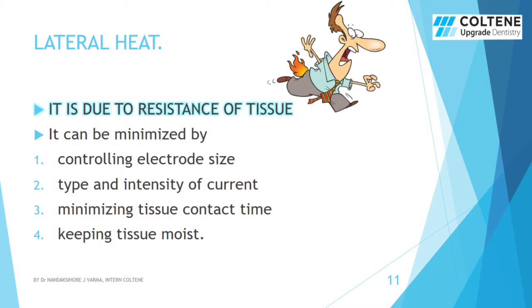Lateral heat is the heat which is caused in the surrounding area of the usage spot of electrodes, caused due to the resistance offered by the tissues. How can we minimize it? By controlling the electrode size and making it smaller, the lateral heat can be reduced. Type and intensity of current, minimizing tissue contact time — just in seconds we can move the electrodes — and keeping the tissue moist.